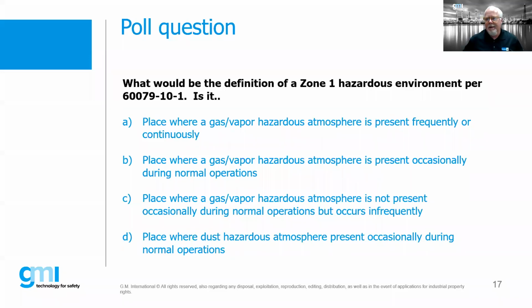Right. All right. I think our guys have answered correctly, right, Bob? Yeah, for the most part. So a continuous hazard would be considered a zone 0, right? And the correct answer in this case would be B, where a hazardous atmosphere is present occasionally during normal operation. Again, we expect to have a flammable gas air atmosphere present at some point in time, but it's not continuous. And then certainly answer C is not present occasionally, but it will occur infrequently.